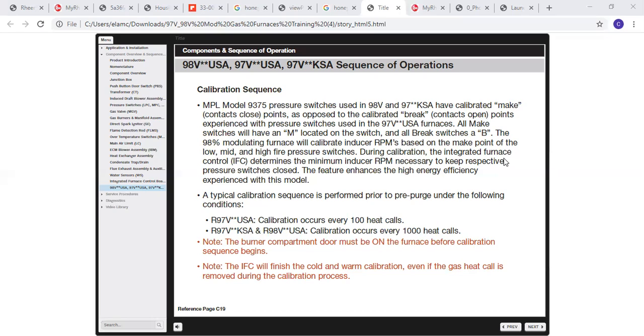When you're doing this, you have both doors on, just like it's in normal operation. If you do leave the door off during the calibration sequence and you put the door back on, then it's going to completely change the dynamics, because it's going to learn with the door off what those points are, and if you put the door back on, now it's not going to calibrate correctly.